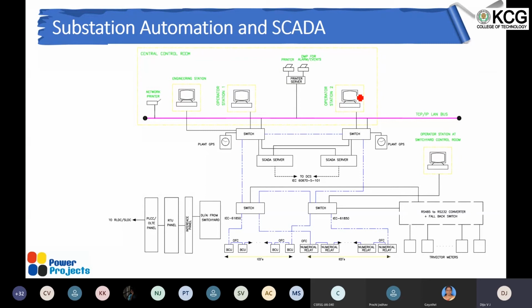We convert it into the digital format, and then it's transferred through the communication network to the SCADA PCs at the control rooms, and the same network is used for controlling the devices also. The BCU is a bay controller unit, so it can measure the information from the CTs and VTs, and it can control the breaker for a close or open operation. So SCADA is basically supervisory control and data acquisition software, which is always used in transmission substations for control.